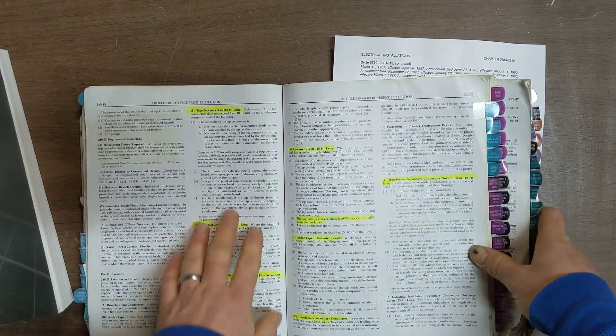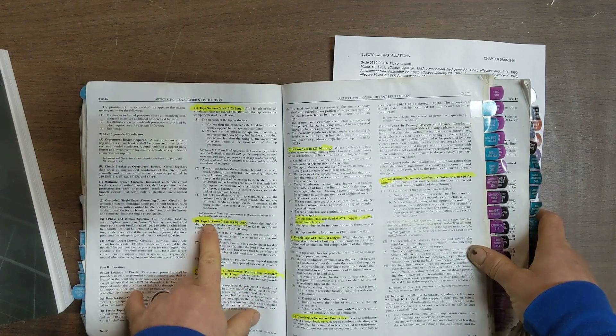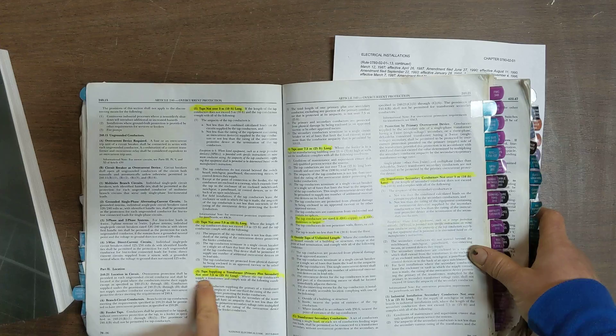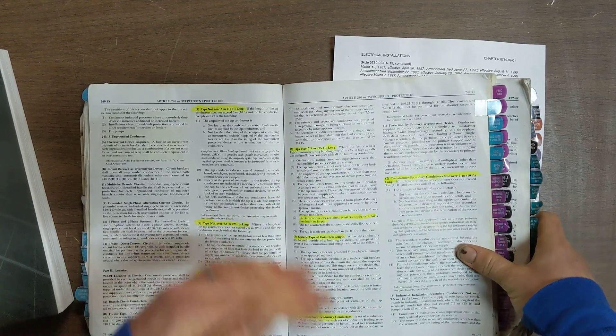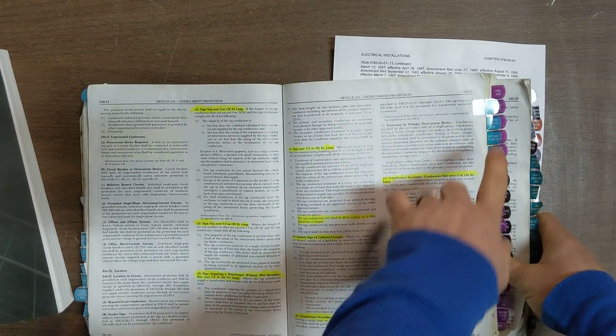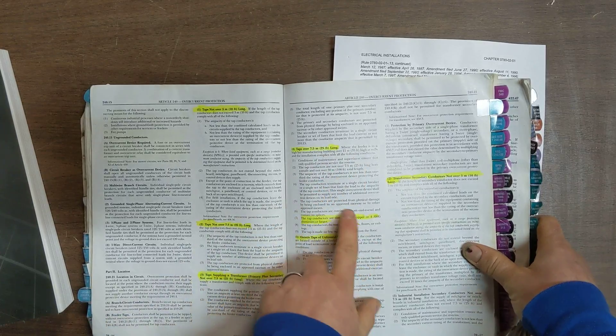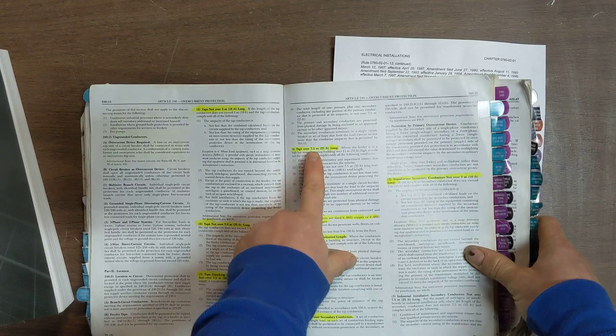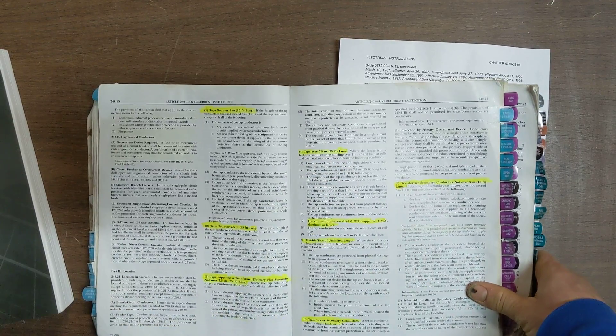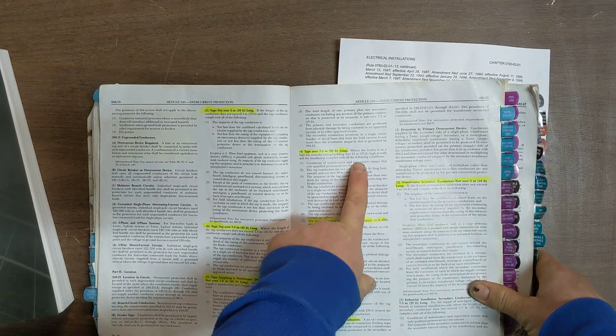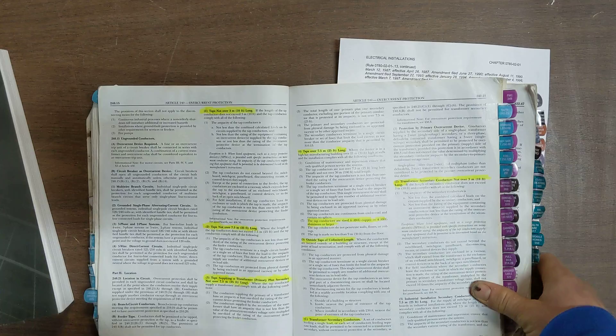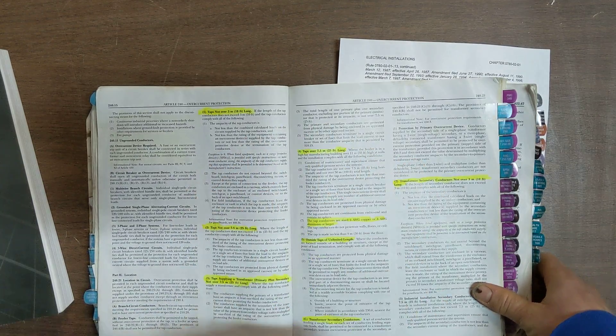So we're moving here. We're going to say it's to do with tap conductors. Article 240. So I know my taps. I flip here. Now I have to look at my black bold headings. I know it's about taps. My question is asking about 25 foot long or over 25 foot long. So not over 10 foot. Not over. Oh, excuse me. Not over 25. Mine's over 25. Supplying primaries. Nothing to do with me that are over. Not over 25. Right here. Taps over 25 foot long. So I come to my keyword. Got me to the taps. You know, use my index. If I needed it. I knew where this tab was. Save me a minute on my time. I come through here. I start looking at black bold headings. If I can't find what I read, I'll start looking at the subsections. I'm looking for over 25 foot long. So the only thing my eyes need to see is when it's over 25 foot long. Then I have to begin to read. It was asking, for instance, you know, you could, I can't make up a question, you know, how many feet can it be high on the wall? Okay, so we got 35 foot on this question. But you want to scroll through and scan what you're looking for and know how to sift out what you don't need.